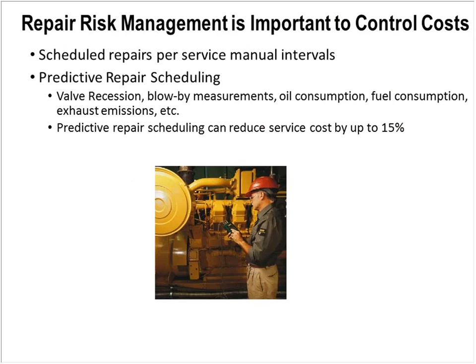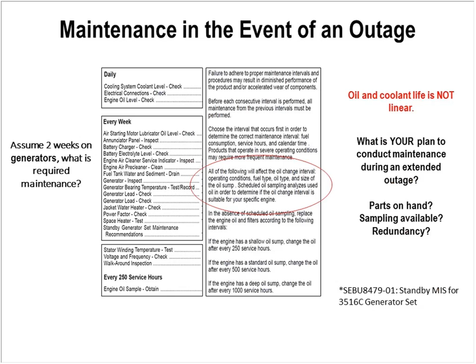The key is that just because I'm in an emergency situation doesn't mean I don't need to do maintenance. So if I'm in a 500-hour outage situation with a diesel engine that requires oil changes at 250 hours, you've got to find a way to do those oil changes, or the unit could fail while in service and standby. Make sure you're servicing these systems so they can run effectively, and make sure you have options in there for that type of system.